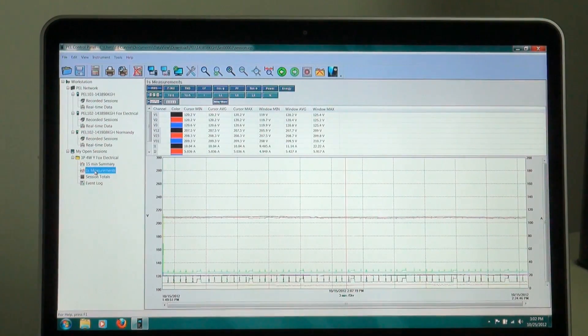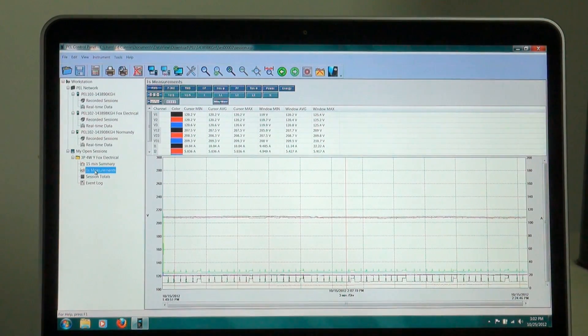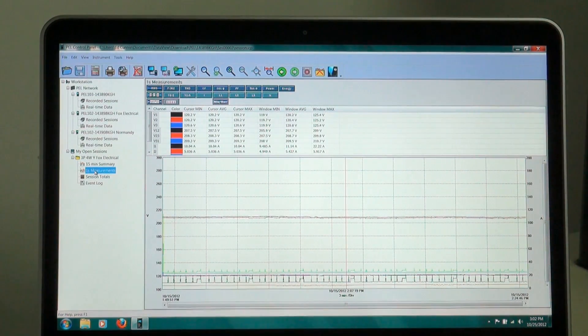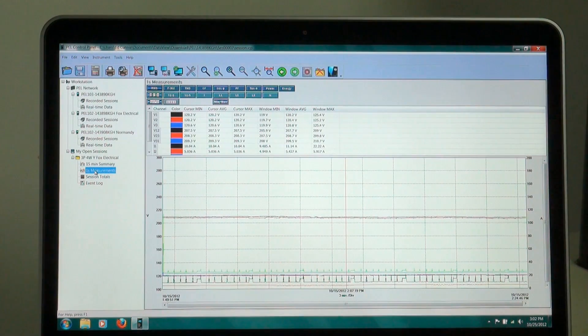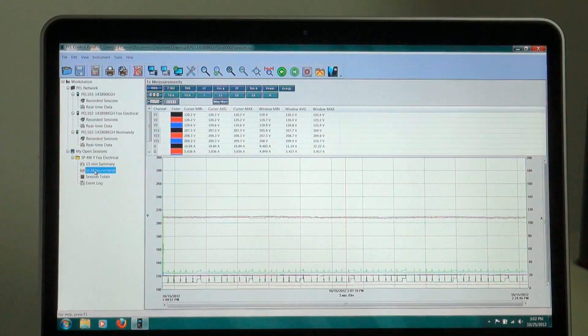And here's my measurements. I can go in and look at the various engineering units over time, and how they changed, and how dynamic they were. Measures RMS voltages and currents 128 times per cycle. And we have a sample rate once every second, and that's our basis for our information. And from that, we can do the 15 minute intervals, the classic utility intervals, out to 60 minutes.